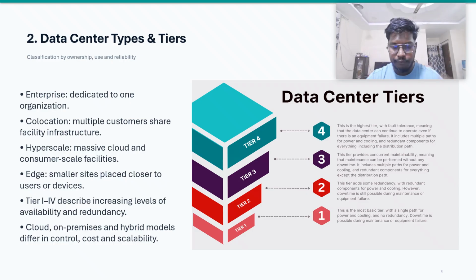We also classify data centers using tiers, from tier 1 to tier 4. If we move from tier 1 toward tier 4, the level of redundancy and availability increases. Tier 3 is designed for concurrent maintenance, while tier 4 provides fault tolerance. If there is any fault, tier 4 level equipment handles its own fault. So the basic difference is this: the type tells us how the data center is used, while the tier tells us how reliable and redundant the data centers are.